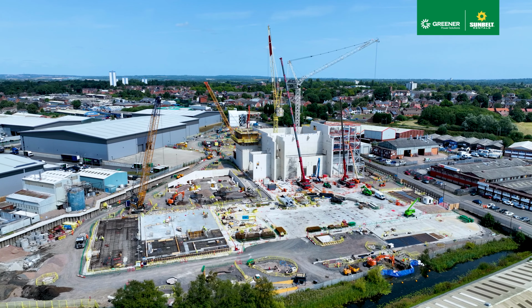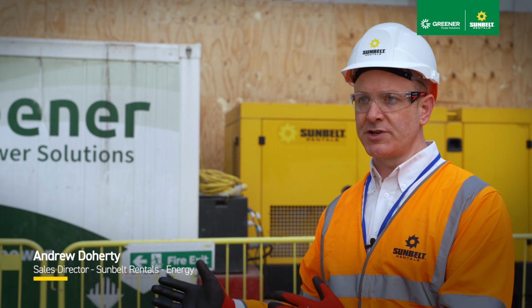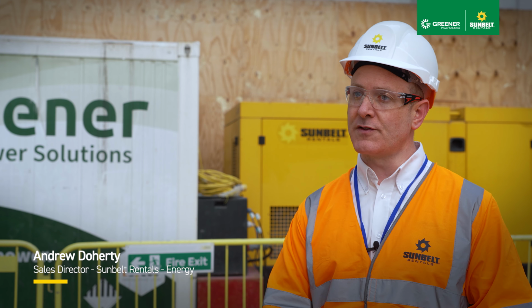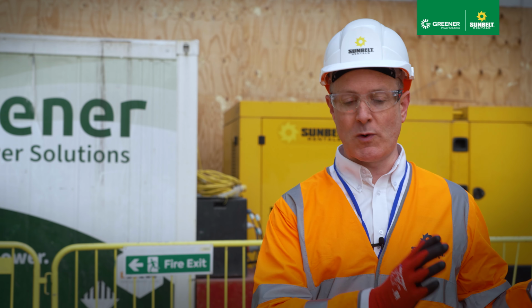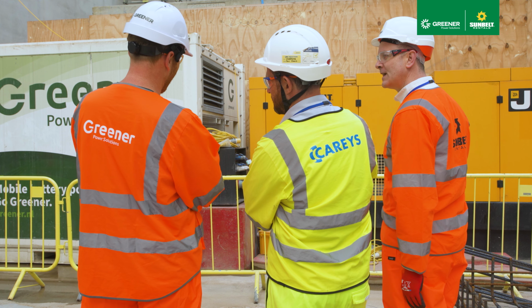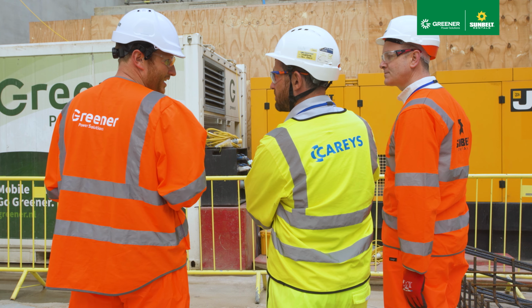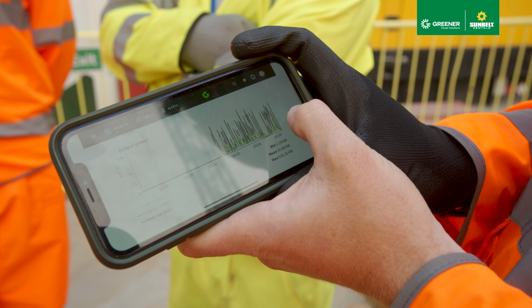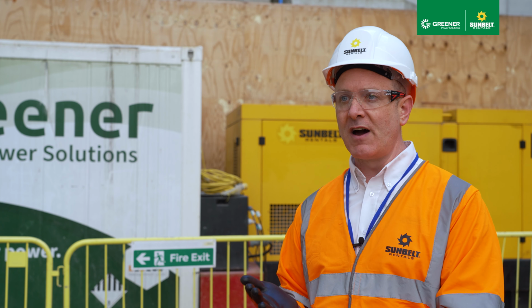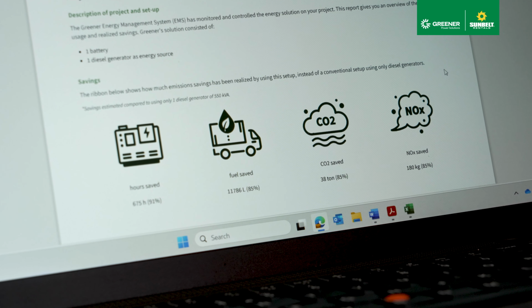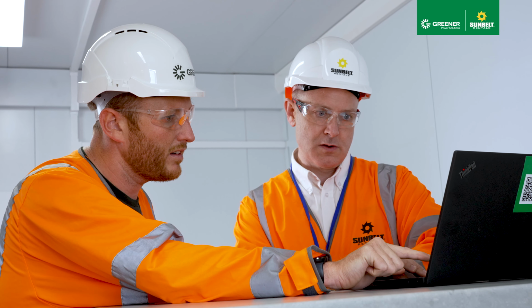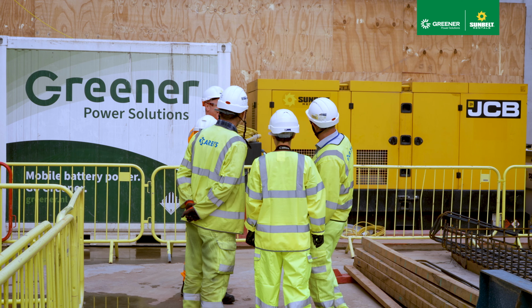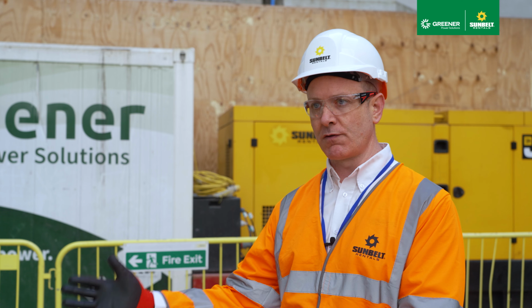By Sunbelt Power employing the greener battery technology, we were able to downsize the generator from what would traditionally have been an 800 kVA down to a 300 kVA, effectively displacing 500 kVA's worth of unnecessary energy. The benefits of that have been significantly less CO2, less fuel usage, and a lot less idle time on the generator, giving the customer a significantly quieter, more efficient power package on site.